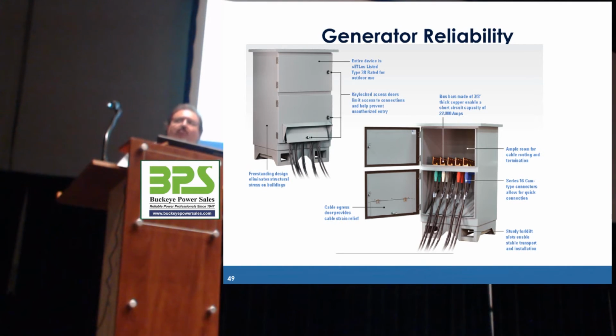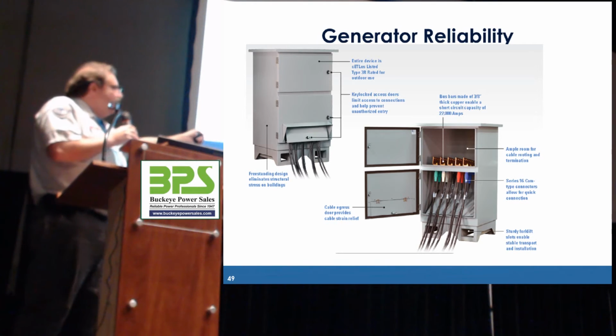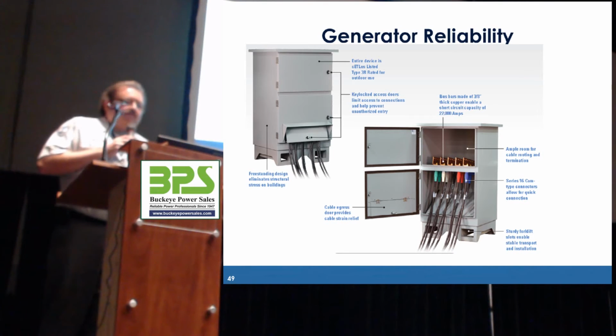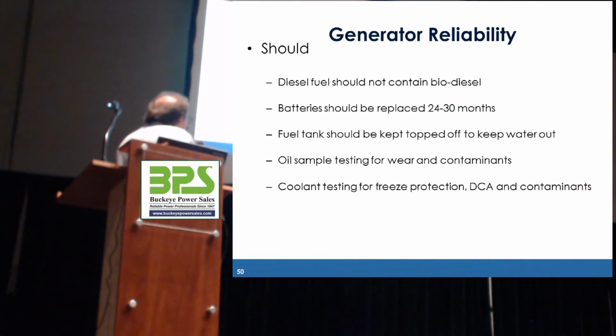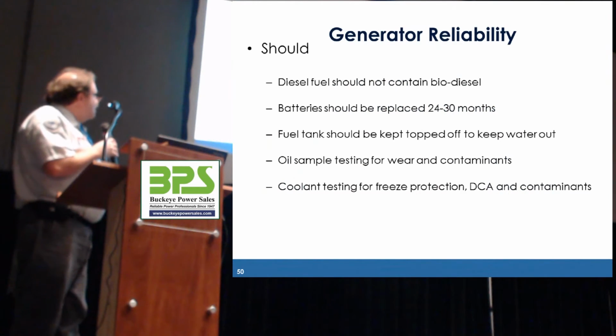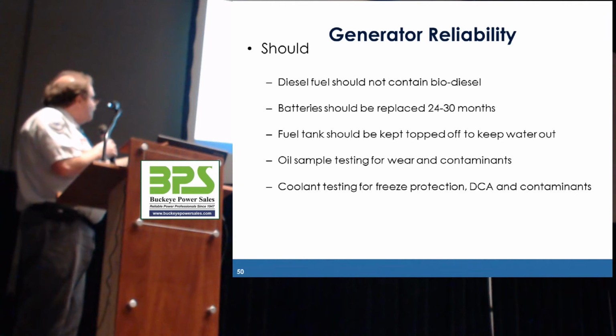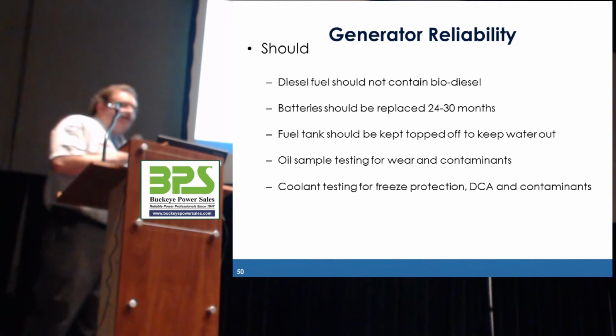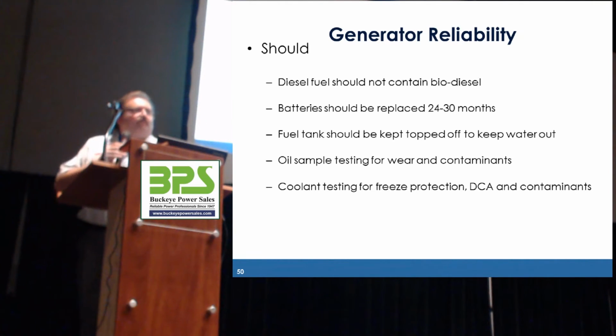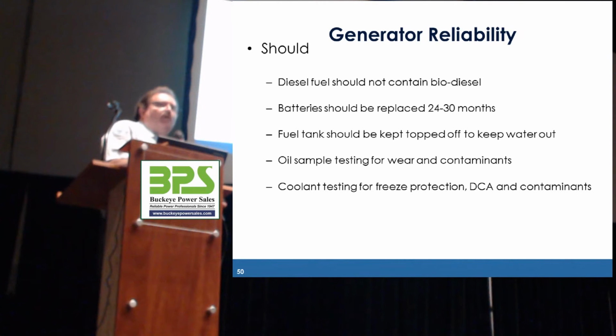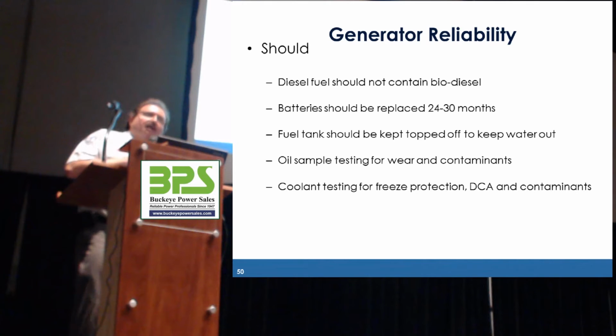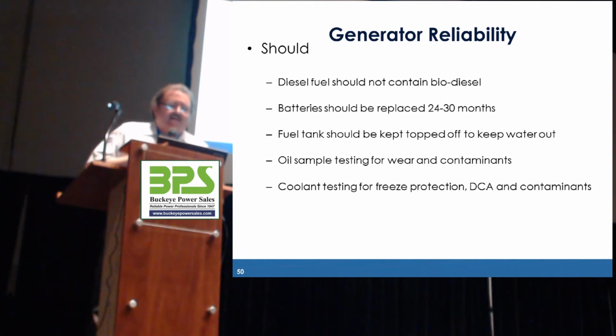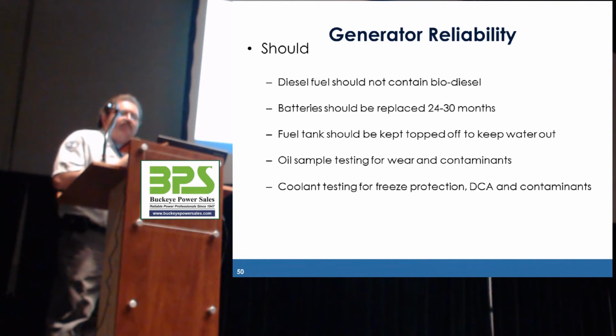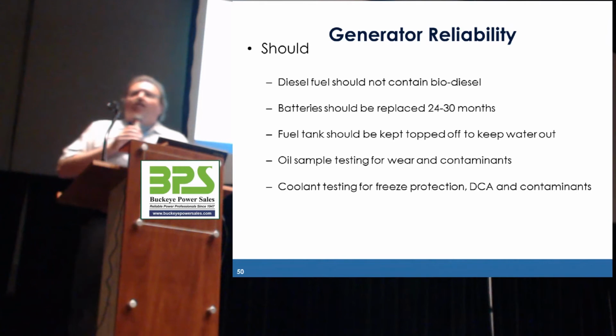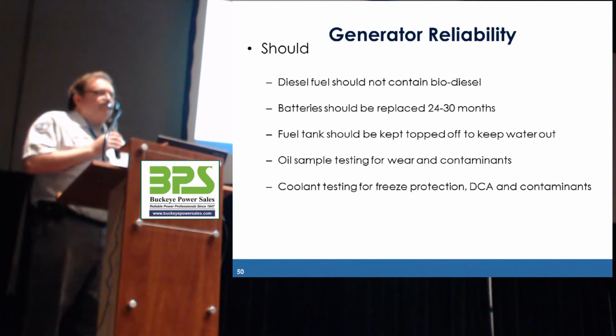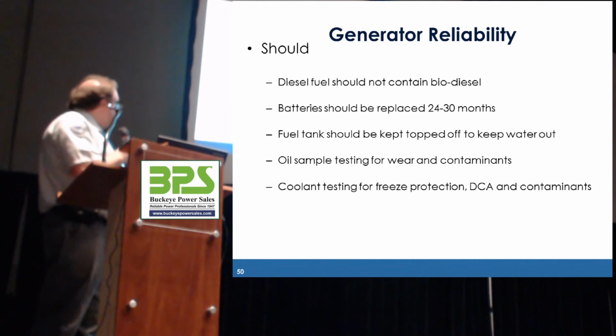Okay? So the infrastructure needs to be there, and there's a number of different manufacturers out there that make devices that have manual transfer switches in them. Some of them do, some of them it's just a connection point for us to hook a load bank up to, also a connection point to hook up rental generators. So it says diesel fuel shouldn't contain biodiesel. We've already discussed that you just don't need to do that. Keep the fuel topped off, replace the batteries. Oil sampling and coolant sampling can be just as important as your fuel sampling. Oil sampling will show you if you have engine wear. Coolant testing and sampling can be a formal lab test, or it can be an on-site test. But you want to look for the freeze protection of the antifreeze, the corrosion inhibitors, looking for dirt, looking for the pH level. So those are all very good things to add into your planned maintenance program.